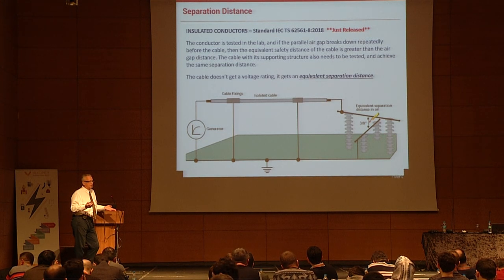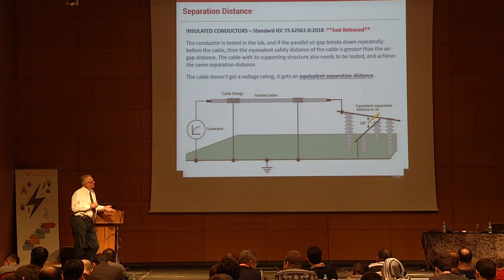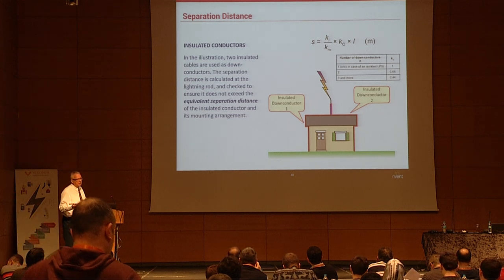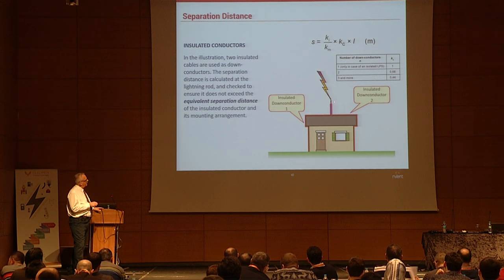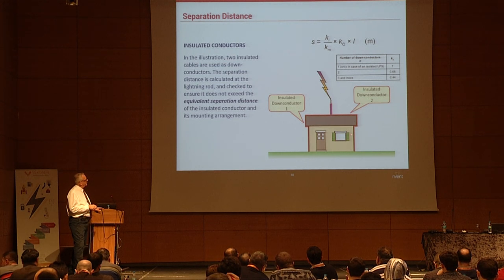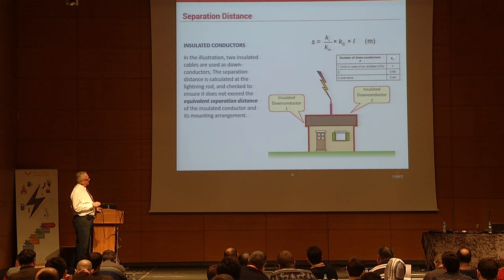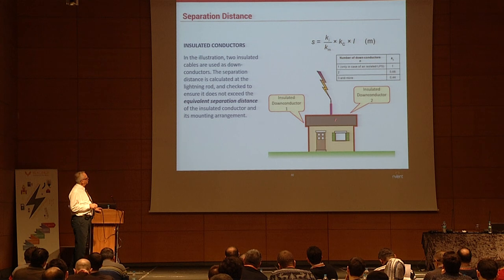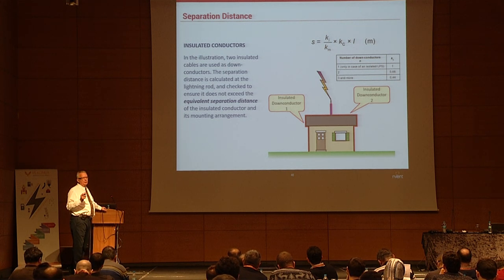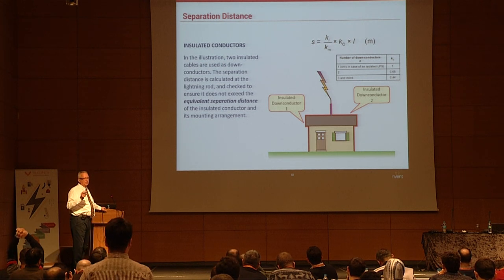By varying the distance — for example at half meter you get a cross flash at the cable, then increasing to 0.6 meters you get a cross flash at the rod, not the cable — that tells you the cable is good to half meter separation distance. The insulated cable can also be used in a structure where the current splits in two directions, applying the Kc factor for single or double conductors. The lab test gives you the separation distance for the insulated cable as well.